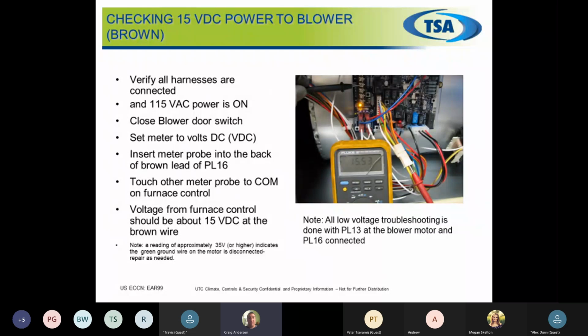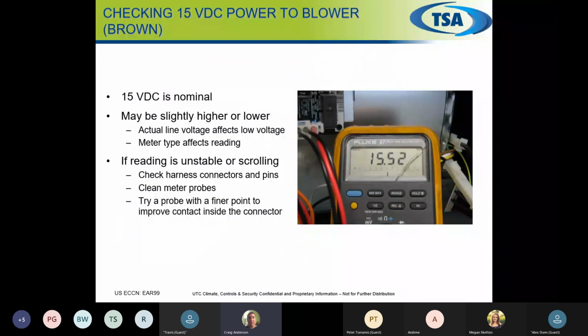Some meters might be a little bit lower, some might be a little bit higher. My tester, if I usually test them, I usually get just over 16 volts DC. So depending on the meter, you might be a little bit lower, you might be a little bit higher, but it should be a constant voltage. Lower or higher, it shouldn't be unstable. It shouldn't be ramping up and down. You should have a constant voltage on that brown wire no matter what.